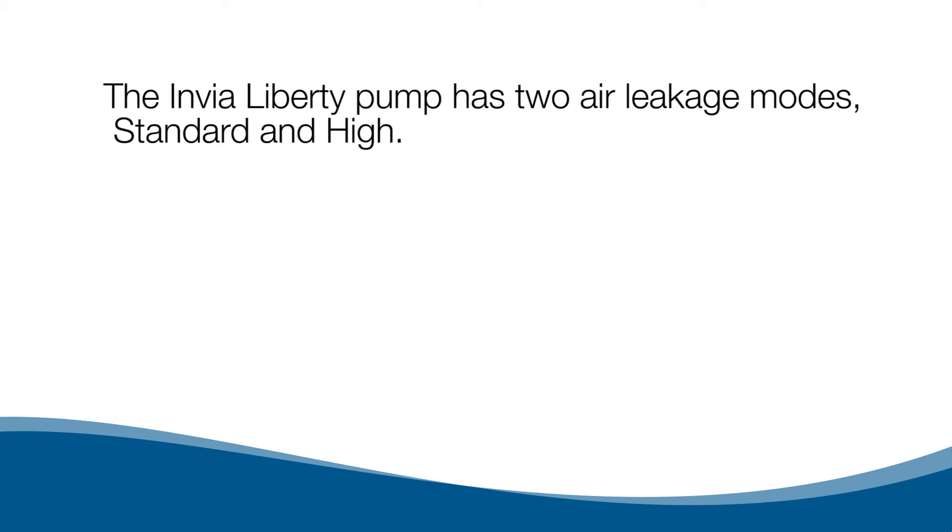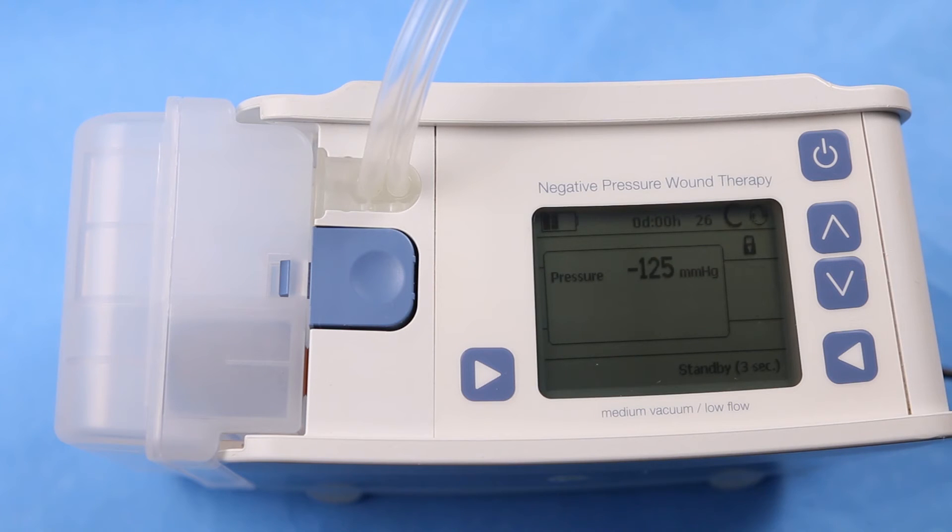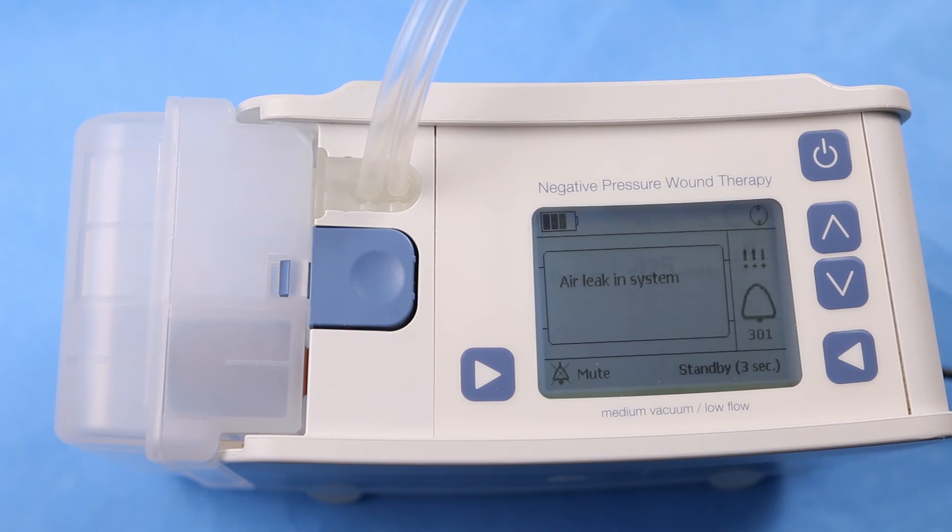The Invia Liberty pump has two air leakage modes: standard and high. In the standard air leakage setting, when the pump is first turned on, an audible alarm will sound within two minutes if the set pressure is not maintained. For larger wounds, use the high air leakage setting. Follow the alarm chapter in the instructions for use. Air leak in system alarm code: 301.